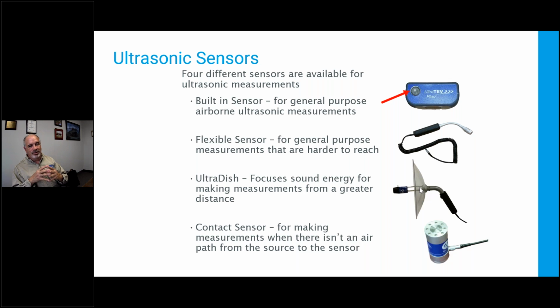The contact sensor is your sensor of last resort. Sometimes you don't have an air gap. You've got outdoor gear. It's got a weather strip around the door. It's got no vents or louvers. You don't have an air path. So you use a contact sensor, and that just connects to the door on the outside and turns the whole door into a sensor. Now, as you might imagine, if I'm looking for ultrasonic waves that are at the level of your eye blinking to vibrate a steel door in a cabinet, it's not going to vibrate very much. So you need a really sensitive sensor for contact. And because it's so sensitive, you're going to have a little more impact of background noise like wind and things like that.